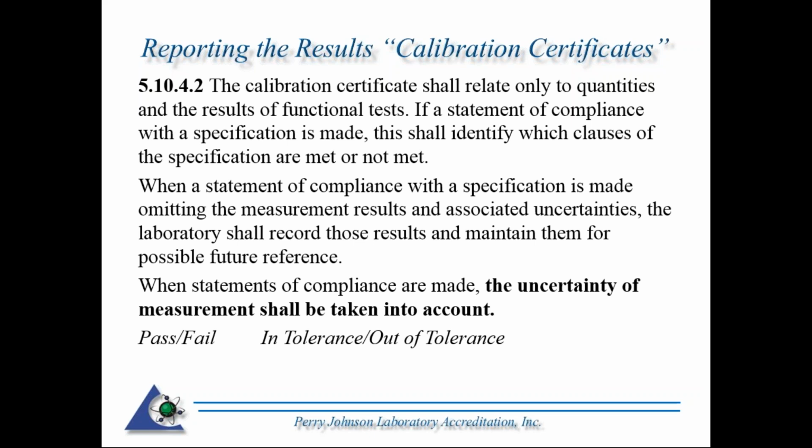So in that case, you may be reporting a pass condition, or if you add the uncertainty into it, it may actually push it over to the fail condition. So before you make a statement of compliance, the uncertainty needs to be taken into account.